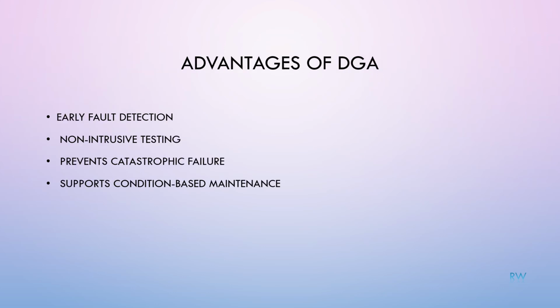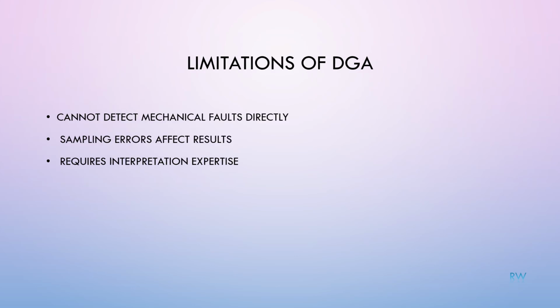DGA provides early fault detection. It is non-intrusive and does not require transformer shutdown. It reduces risk of catastrophic failure. It supports condition-based maintenance strategy. It is cost-effective compared to transformer replacement. DGA cannot directly detect mechanical looseness or external component failures. Incorrect oil sampling can affect results. Interpretation requires technical knowledge and experience. DGA should always be used along with other diagnostic tests.